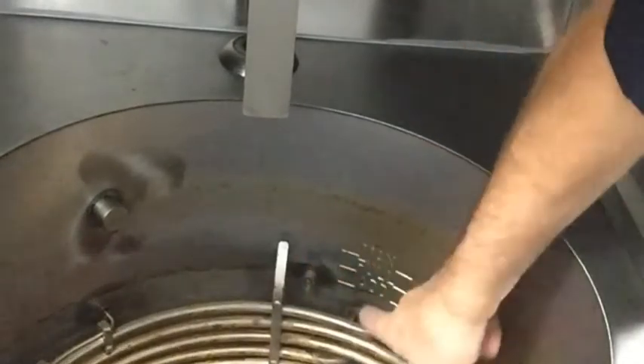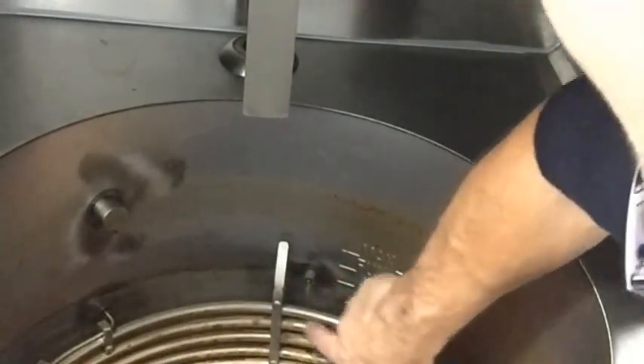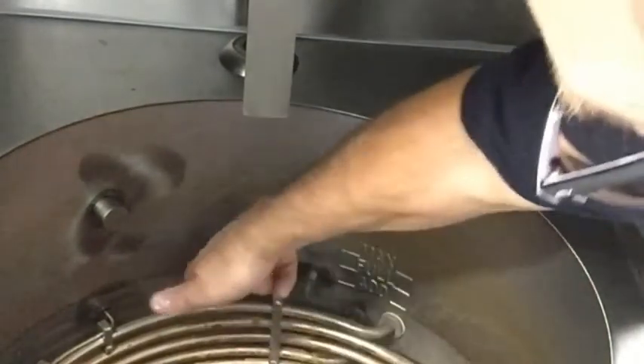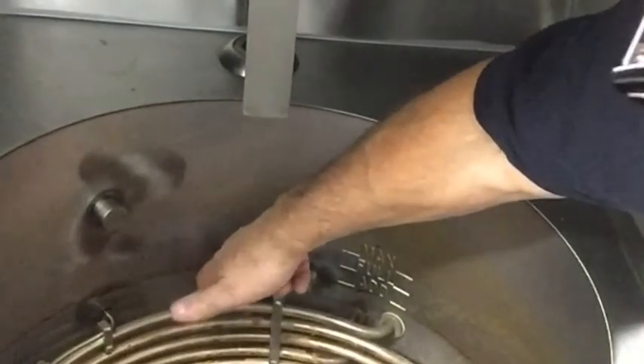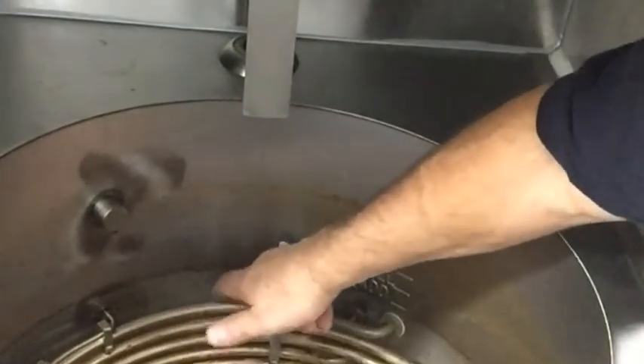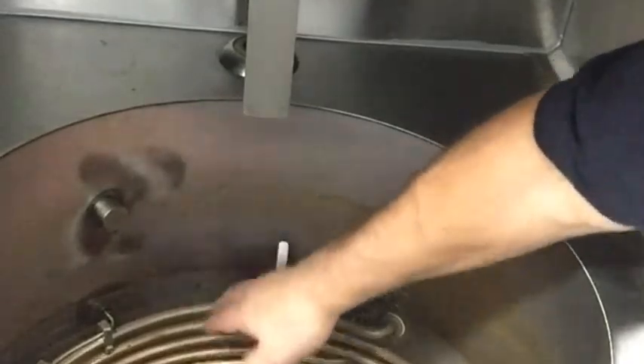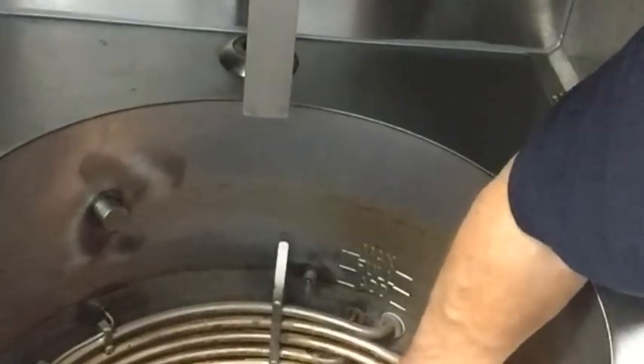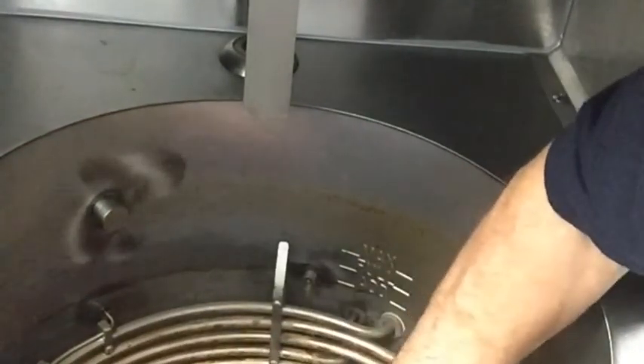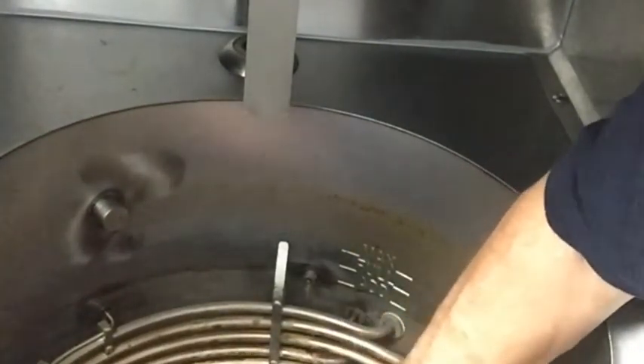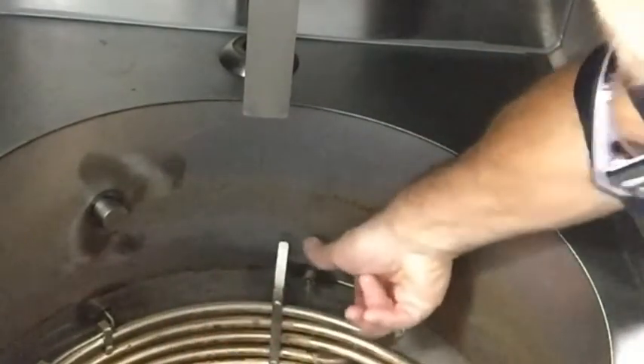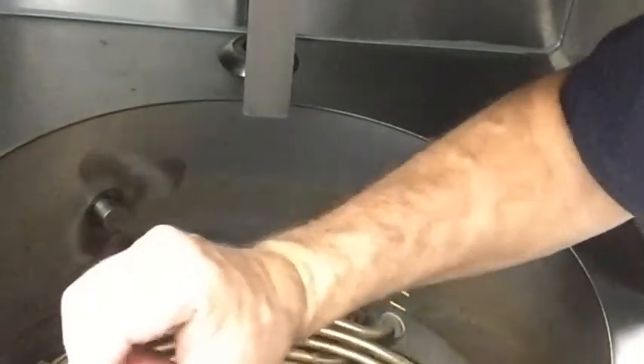This is your high limit probe. It comes over, runs through this bracket, and then it is bent just to the outside of the elements. So if the oil gets over 450 degrees, it will shut it down. Okay, and just below the high limit probe is your actual variable probe, the one that is controlling the oil temperature. So if you're ever going to check calibration, that's where you want to check. You want to try to set your probe right there next to that little short stubby probe.